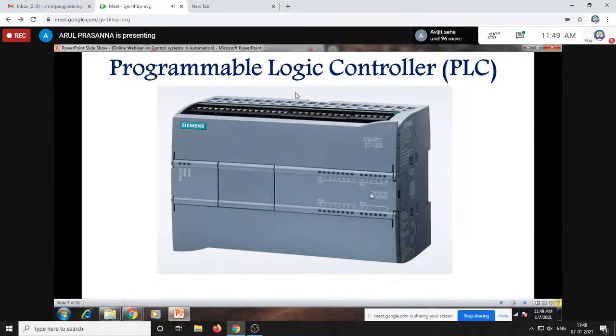Each PLC has two sets of units: an input unit and an output unit. The input units are called digital inputs, DI, and the output terminals are DOs, digital outputs. Along with DI and DO, some modules also have analog inputs and outputs, which fall under analog processing PLCs, with additional terminologies AI for analog inputs and AO for analog outputs.